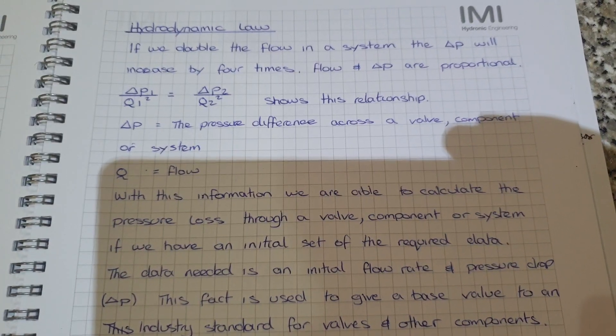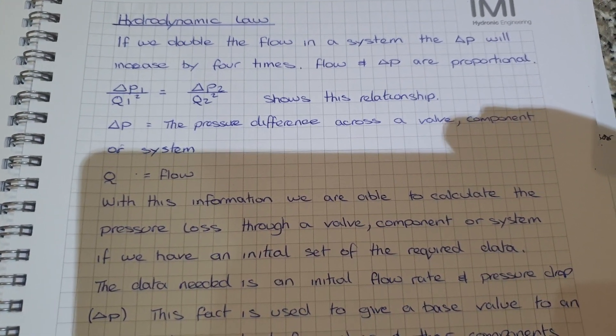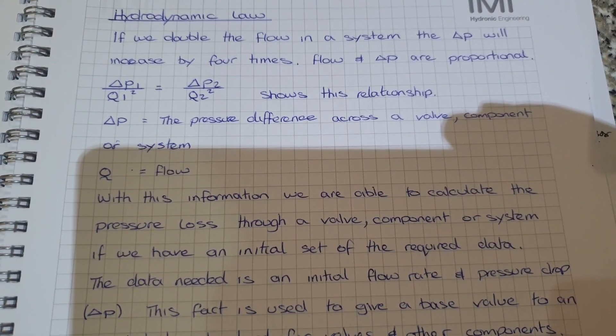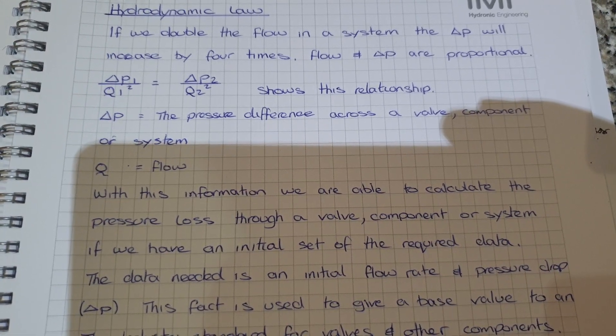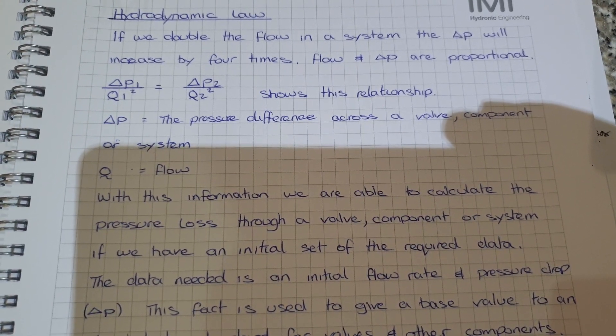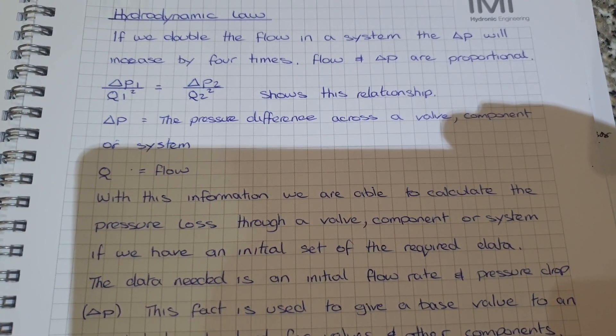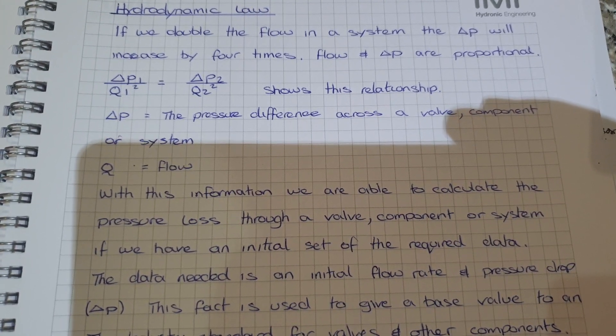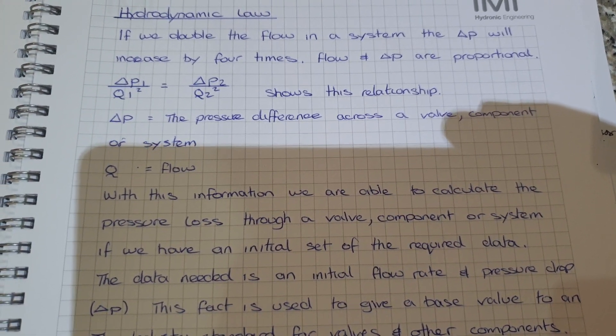The hydrodynamic law, which we talk about on the forum quite a bit, basically says that if we double the flow in a circuit, we'll get a pressure loss across that circuit four times greater than before the increase in flow. That's the same for valves.